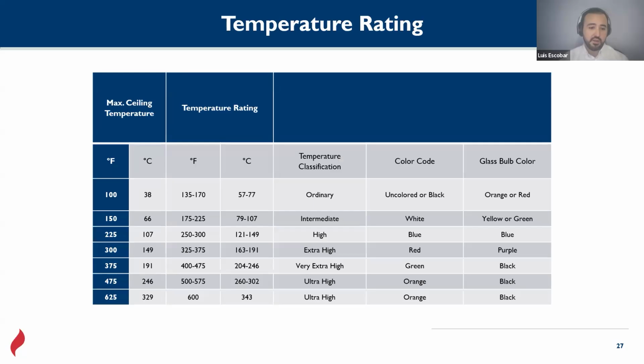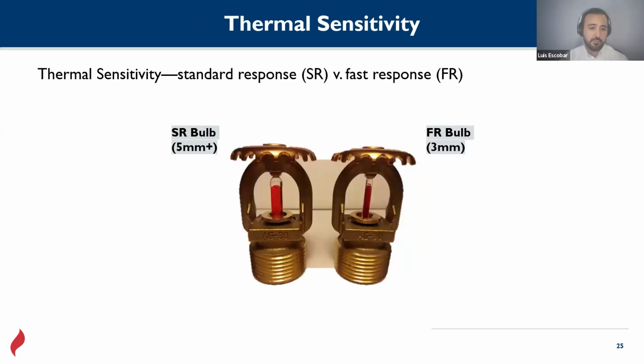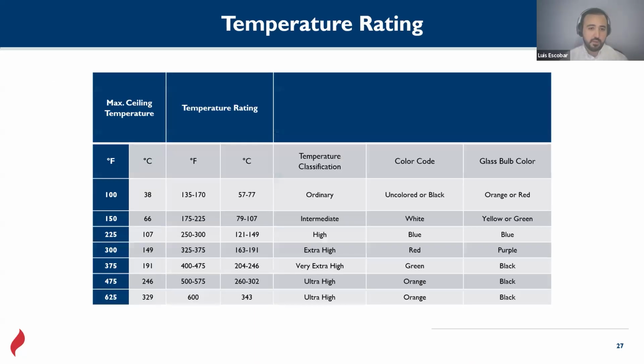Temperature rating, you see here in this one that it's red. The fluid inside the bulb is red. And it's going to take us to the temperature that they're rated. Orange or red means 135, 170 degrees to break the bulb. What happens is the heat penetrates the bulb, starts heating the fluid, which expands, and when it expands, it breaks the bulb, and the water starts flowing.